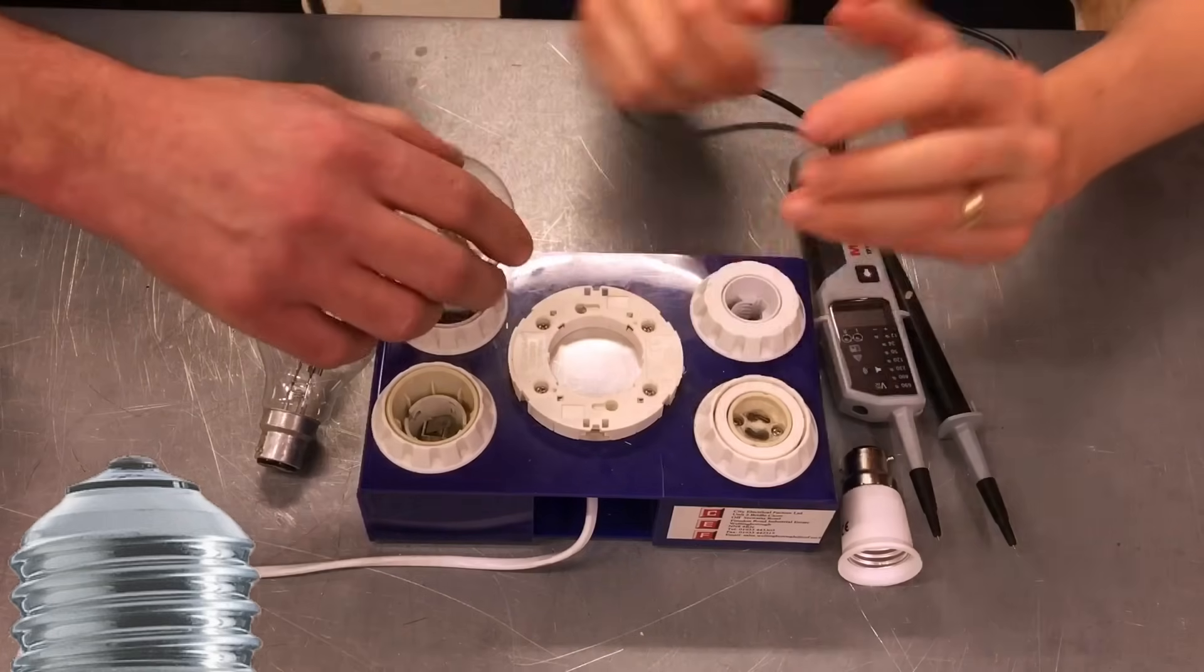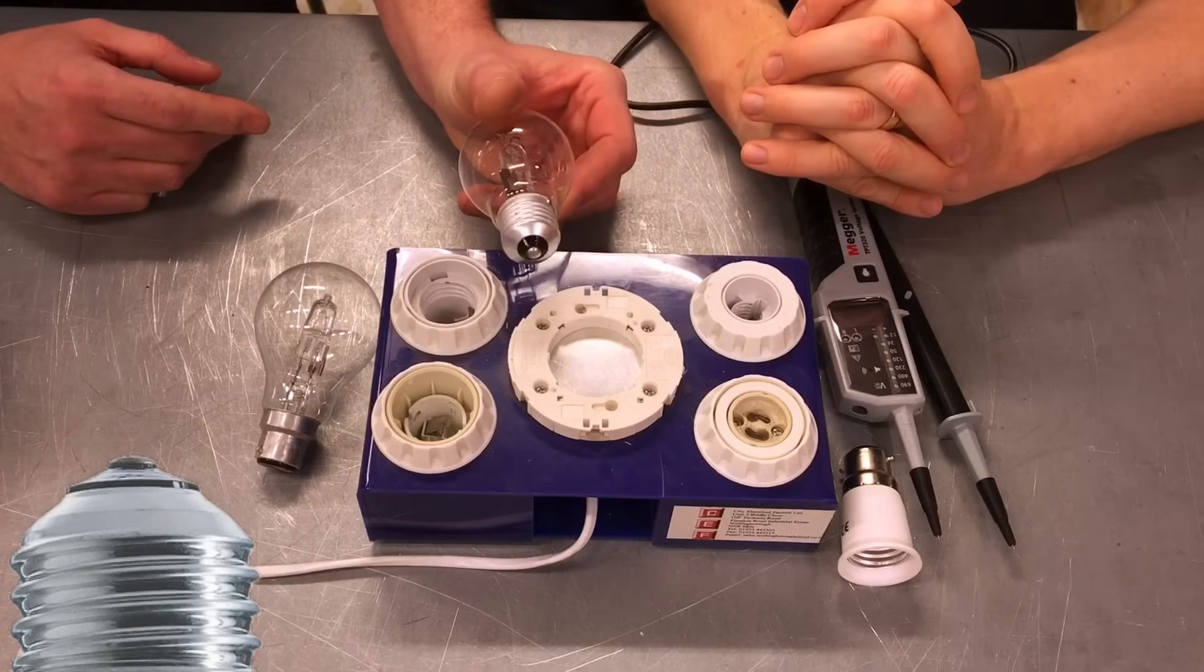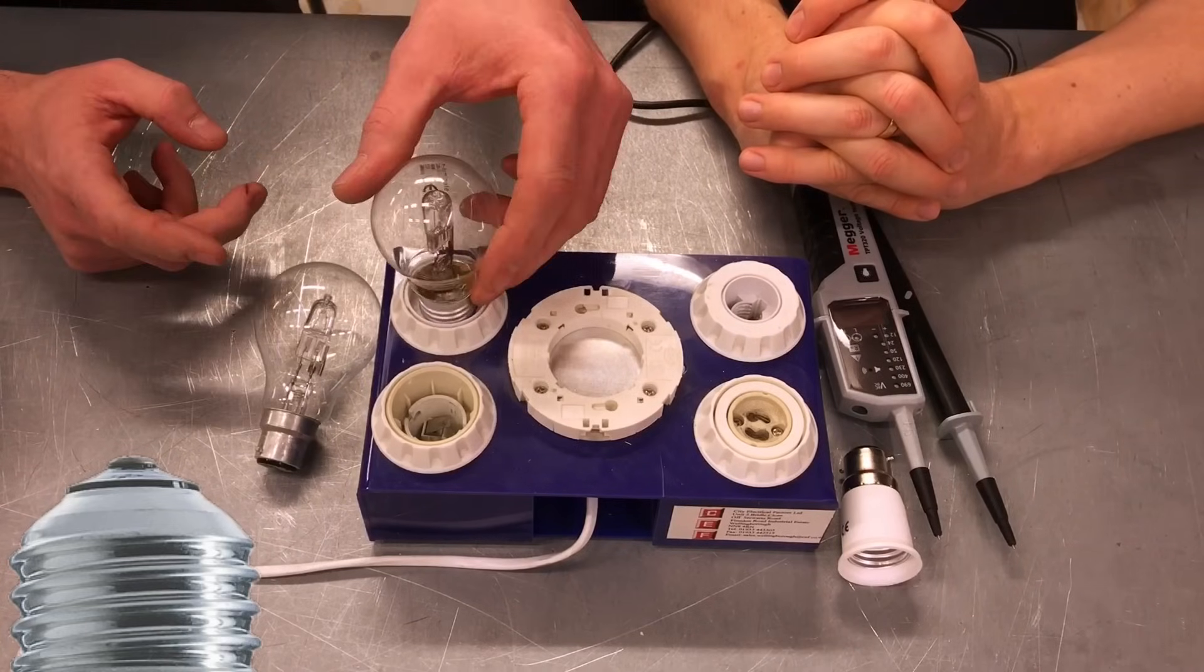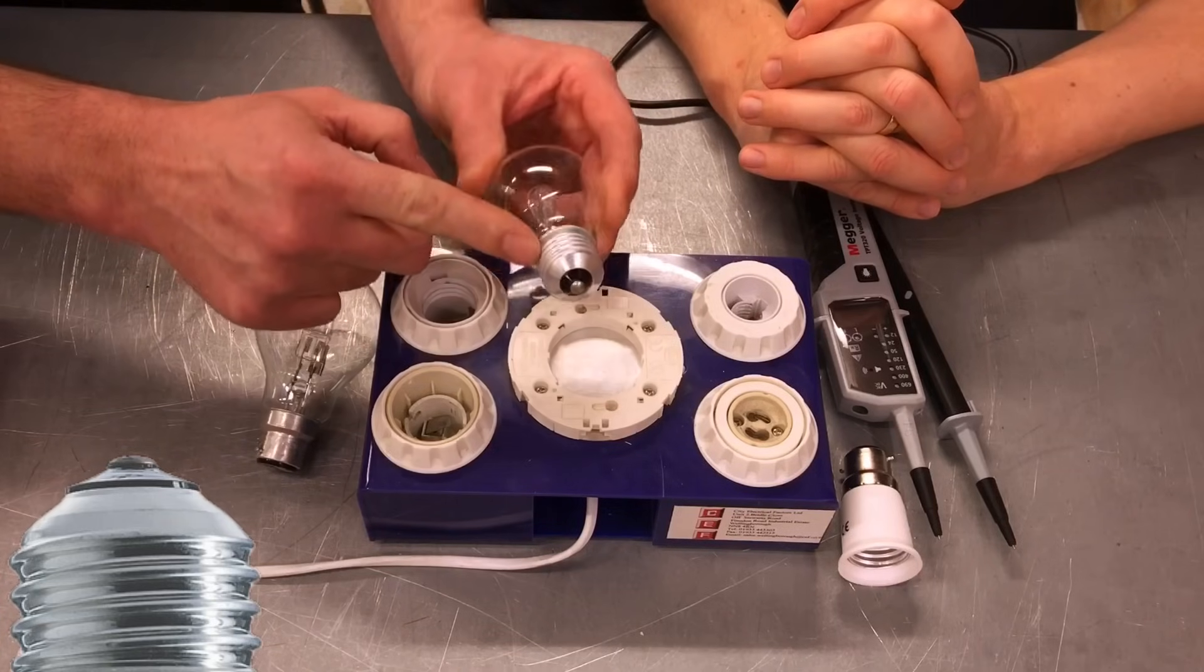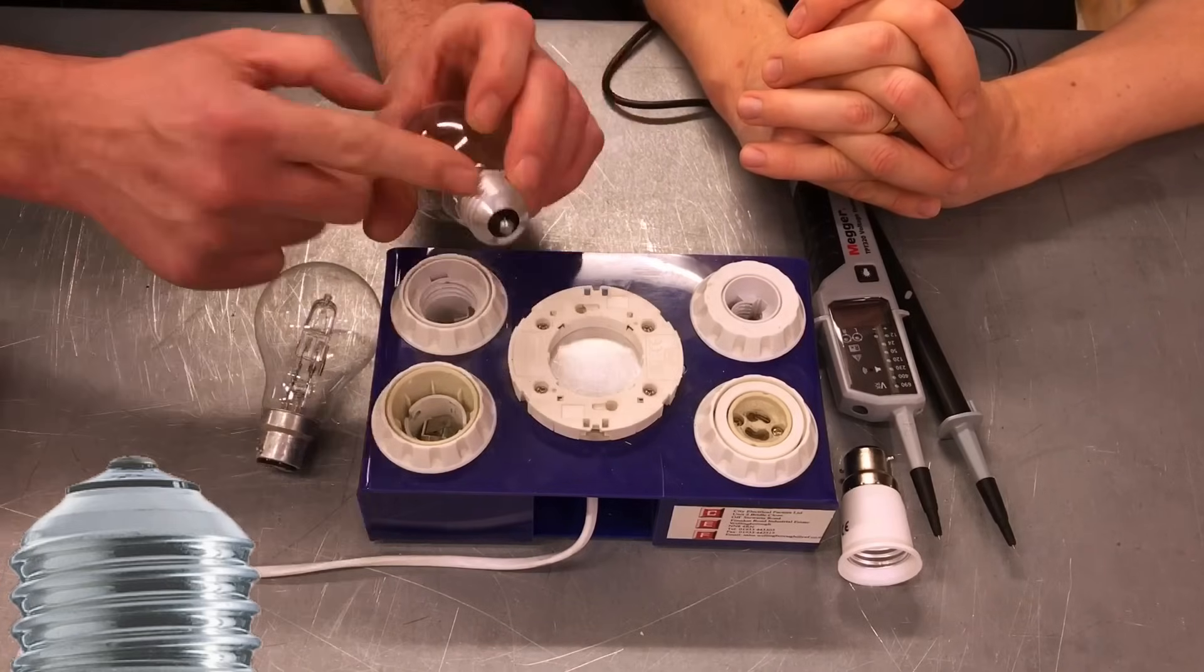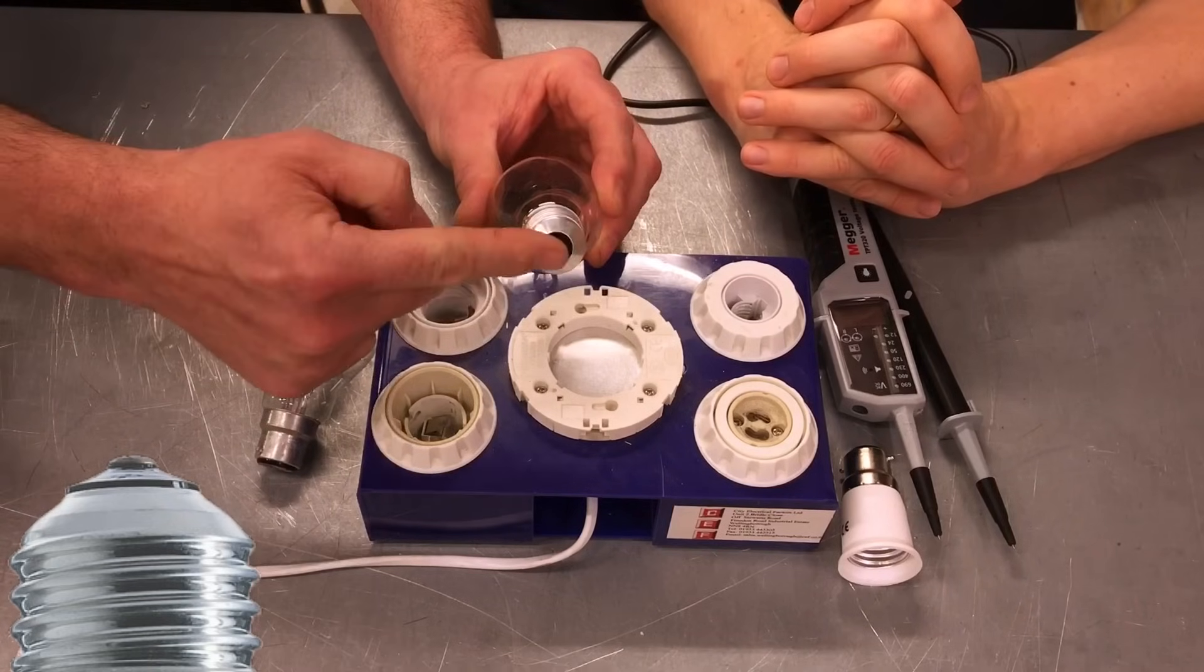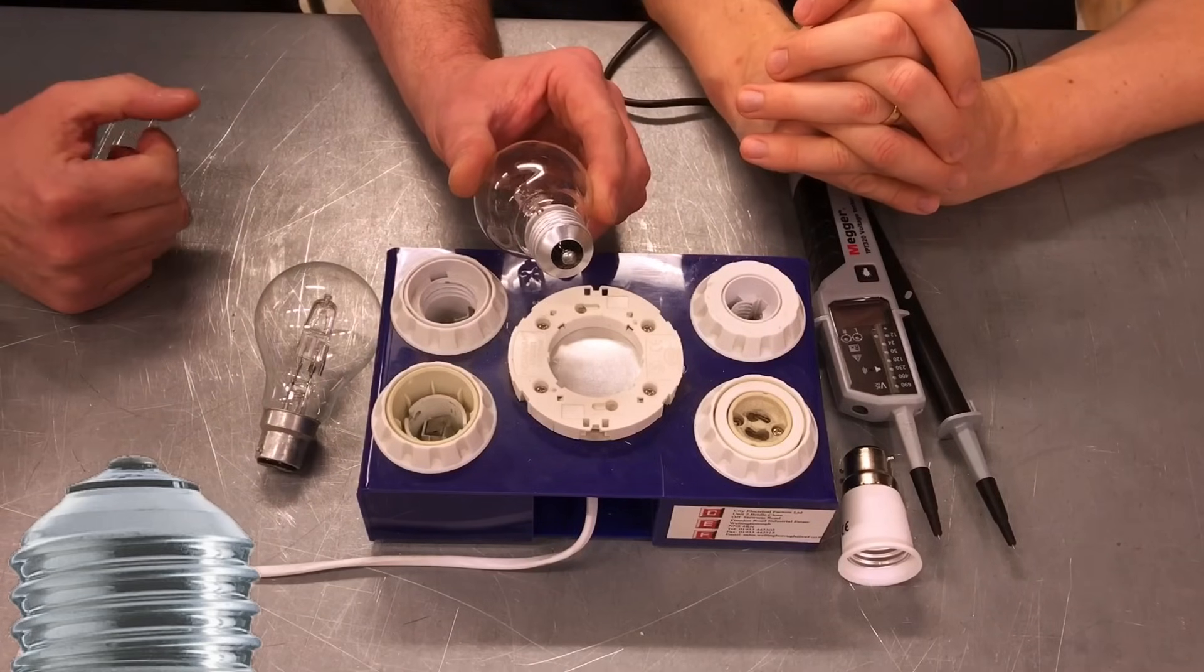BS-7671 requires us to prove polarity of all Edison screw lamp holders, being line and neutral, because when we insert it into here like so and start screwing it down, we can actually touch the screwed element. If that screwed element here was actually connected to the line conductor, as the customer goes to screw it in, they can certainly touch the screwed part connected to line, obviously a massive risk of electric shock. So it's vitally important that we get the line conductor here and the neutral conductor here, and we prove it during our testing process.